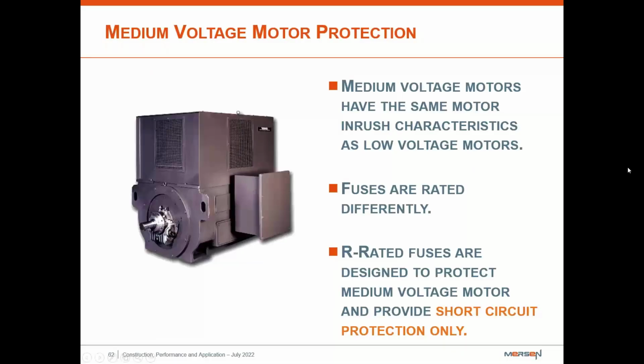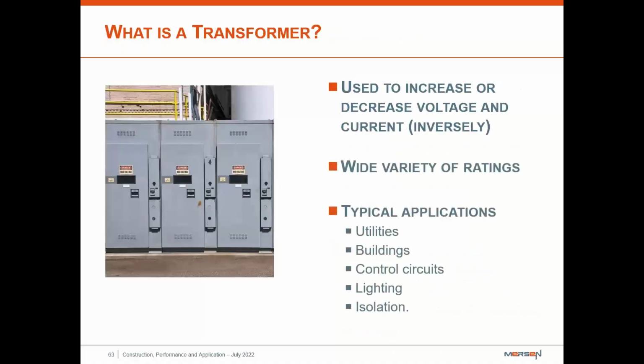So medium voltage protection. In this application, you're not allowed to use a fuse for overload. You're supposed to be using R-rated fuses for short circuit current protection only, which means that they're required to have an overload relay to protect any medium voltage application. So let's jump into a transformer.